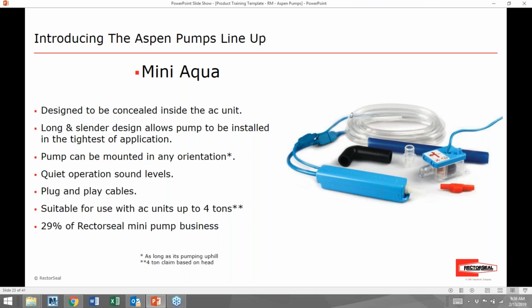This pump does operate around 20 decibels, again, which is very, very quiet, not audible to most humans. But again, the pump mechanism itself can make some vibration. And so simply by using good common sense and using some insulation materials such as Armaflex, you can usually quiet any vibration transfer. The Mini Aqua does have plug-and-play cables, so coming off the pump, you'll have about 5 inches of cable with a plug, and those 2 plugs will plug into, one will go to the power, and one will go to the reservoir.